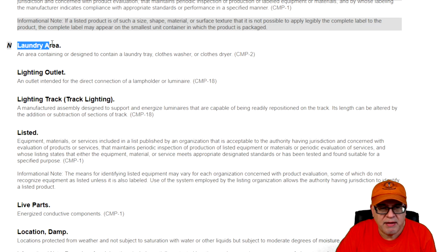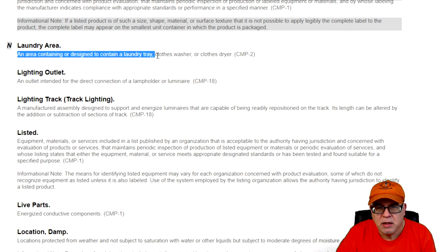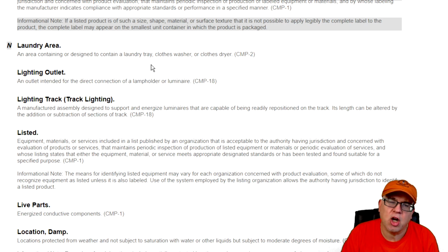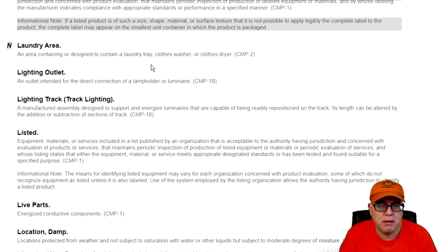Laundry area. We have a definition for laundry area. It says an area containing or designed to contain a laundry tray, clothes washer, or clothes dryer. Okay. Interesting enough, a clothes dryer is not required equipment. Okay. A washing machine or laundry circuit is required, but a clothes dryer circuit or separate 240 volt application to a clothes dryer is not a requirement in the code. However, we do have rules in 220.54 for dryers if we're going to put one in there, and most places do, but you still have the requirement for the laundry circuit.